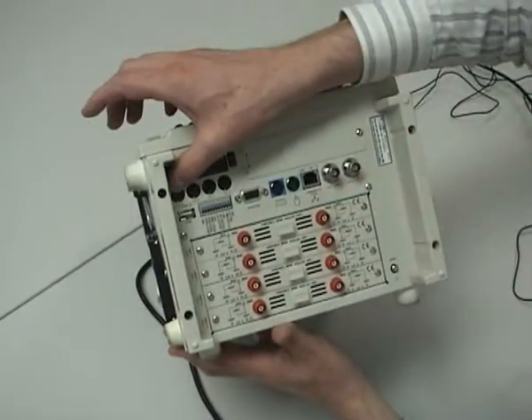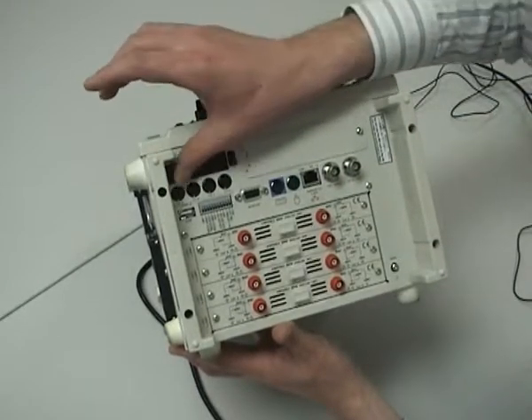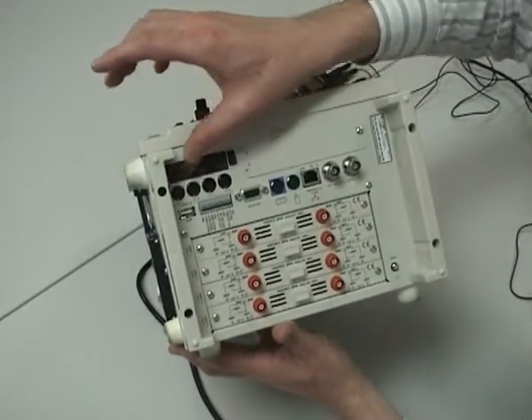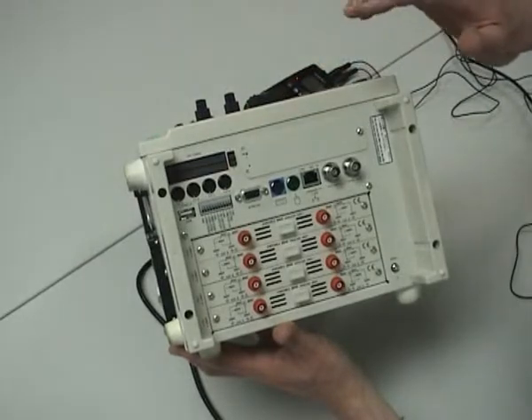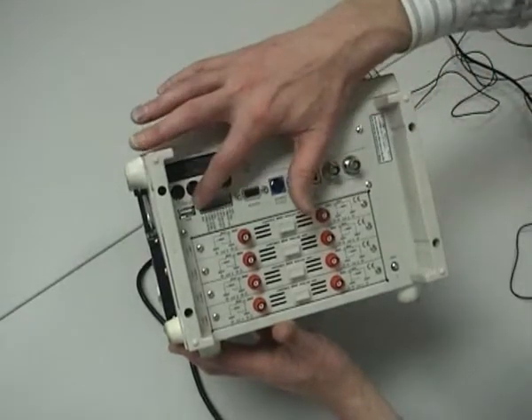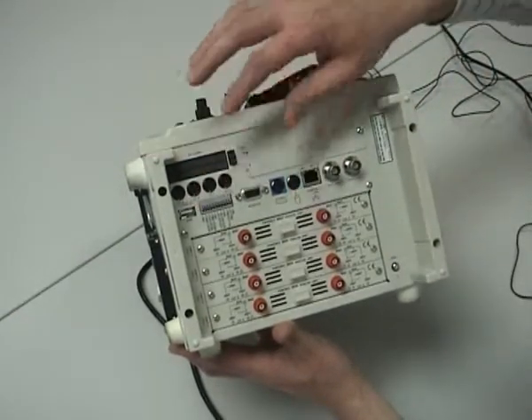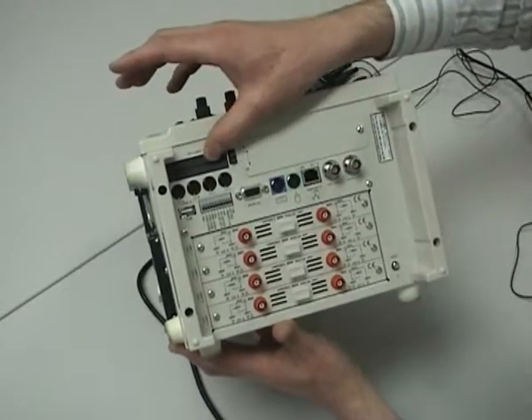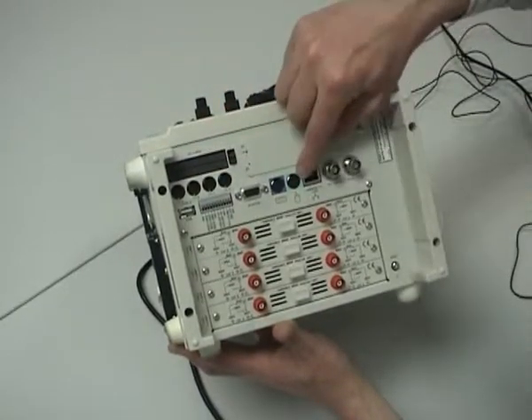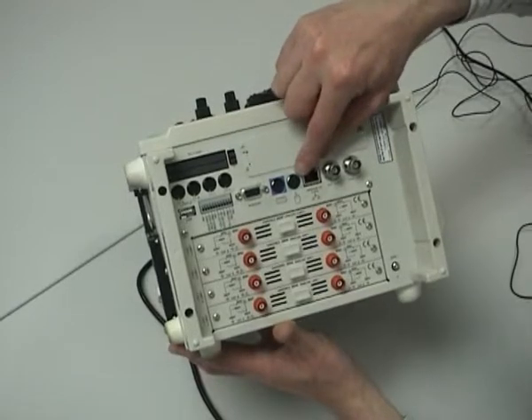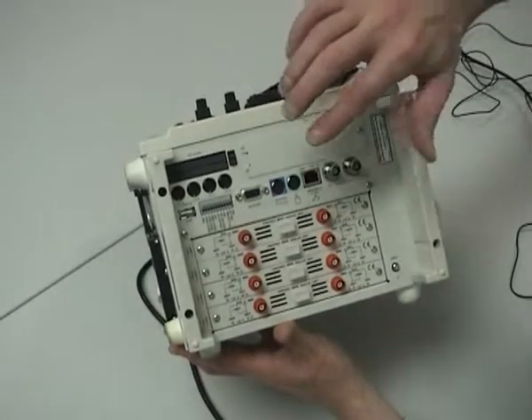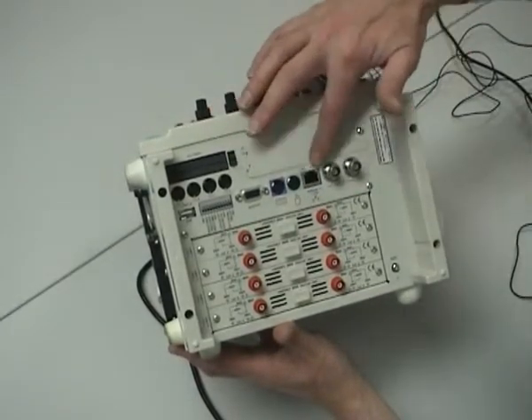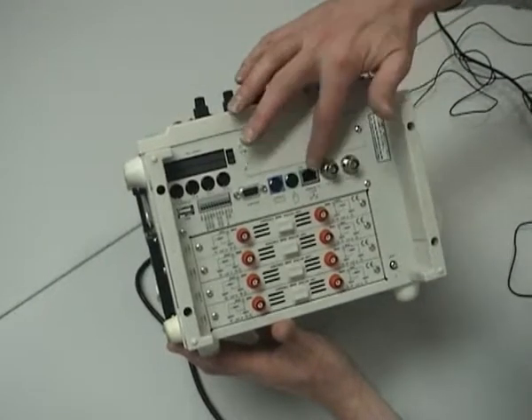We've got some logic inputs here. These are four channel logic units, so you can get 16 logic channels. In addition, there's a USB slot for memory stick storage, compact flash storage. You can add a mouse, which makes it much easier to operate the unit in the front. It's a Windows style interface.